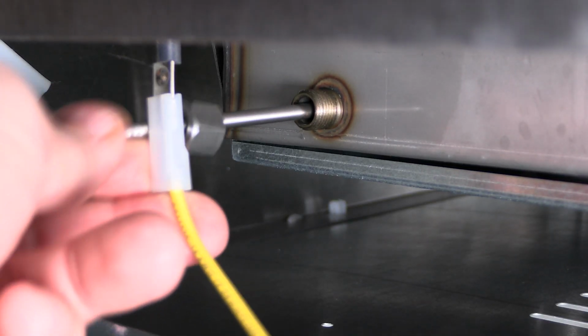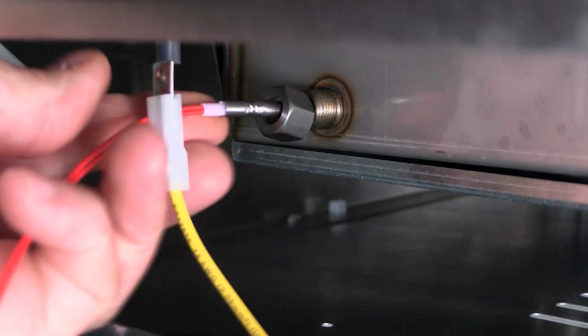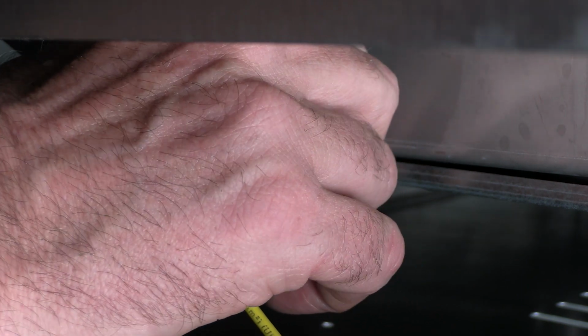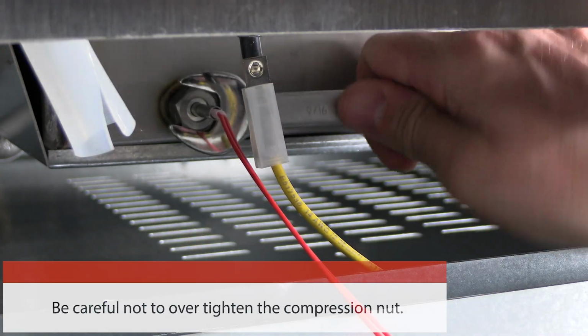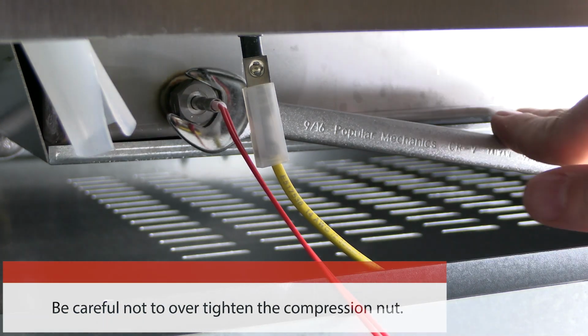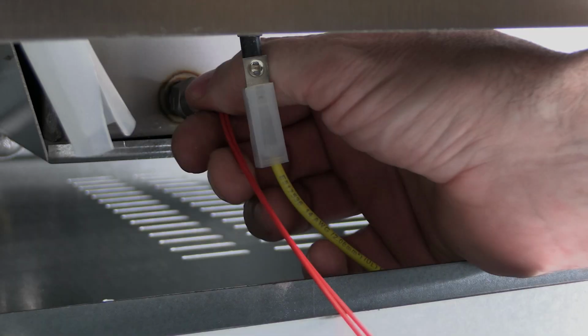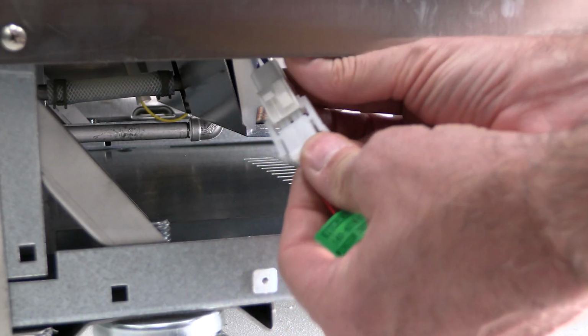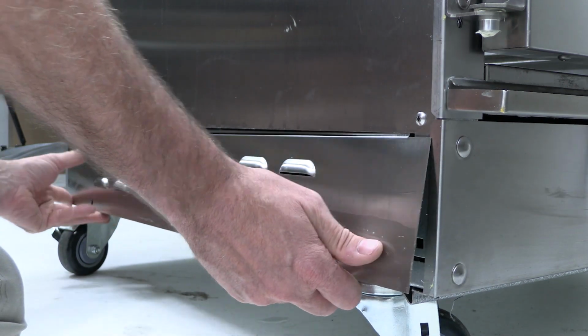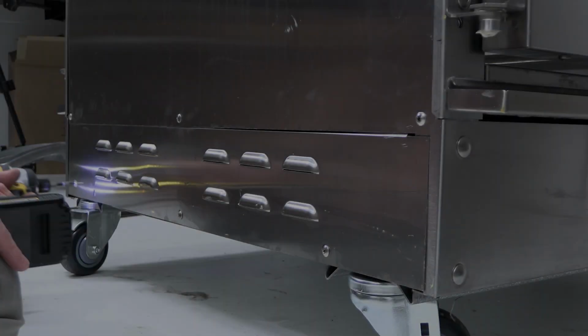Insert the water probe back into the evaporator pan approximately 2 1/4 inches. Using a 9/16 wrench, tighten the compression nut until the water probe doesn't slide in or out. Reconnect the water probe Molex connection. Then, using a Phillips screwdriver or screw gun, replace the lower access panel.